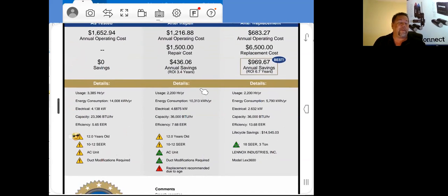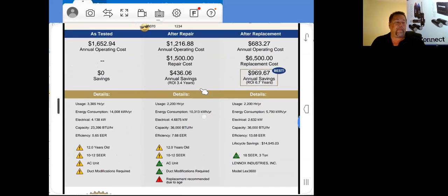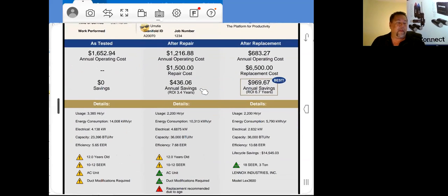The system's 12 years old, it's operating at a low SEER unit. We've got an issue with the AC unit, and duct modifications are needed. If we were going to go in and repair this system, the repair cost is $1,500, which after the repair - you probably just did this, you can always estimate it out - is $1,216.88. So they've got an annual savings of $436.06, and the return on this investment would be 3.4 years.